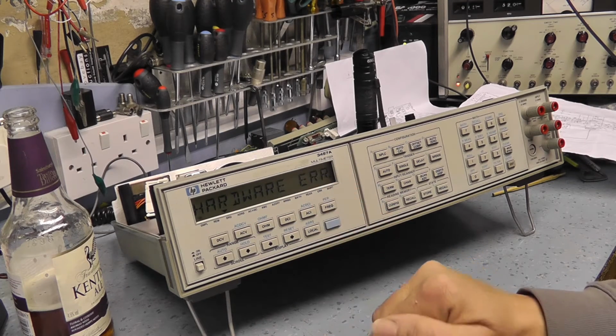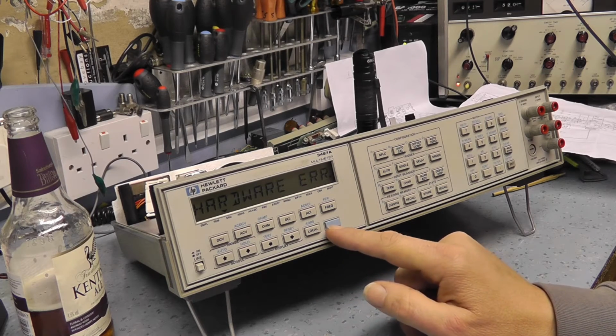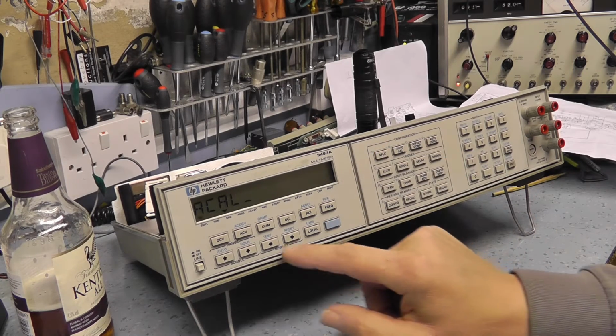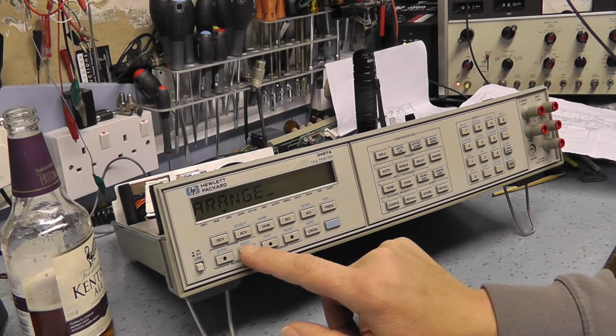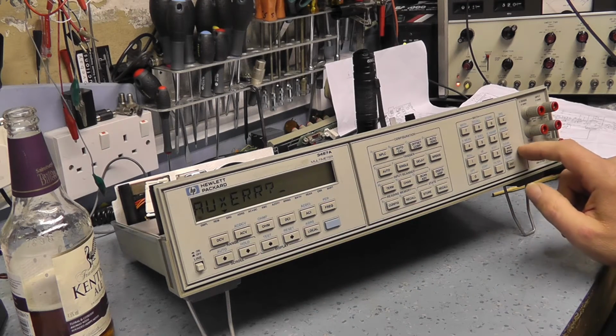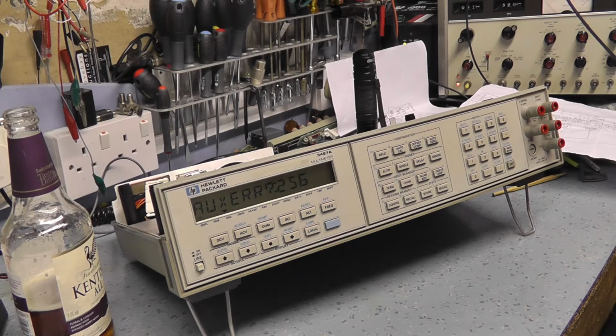Now to see what this hardware error is, you press shifted, number of power line cycles, scroll down to auxiliary error and press enter, and it will show 256, which is AC response flatness error, or out of tolerance.